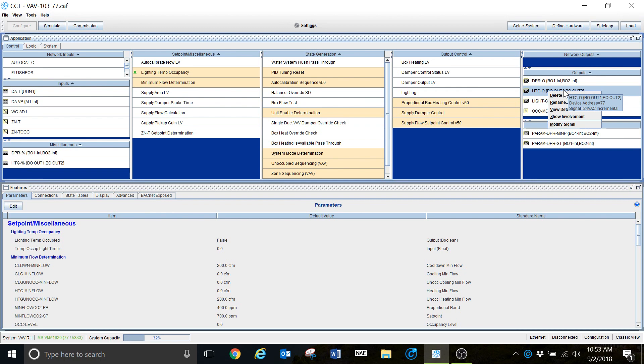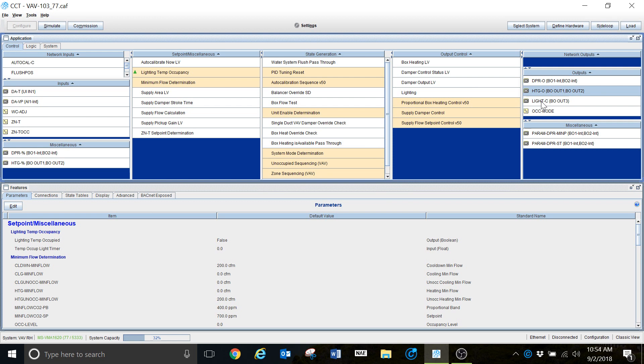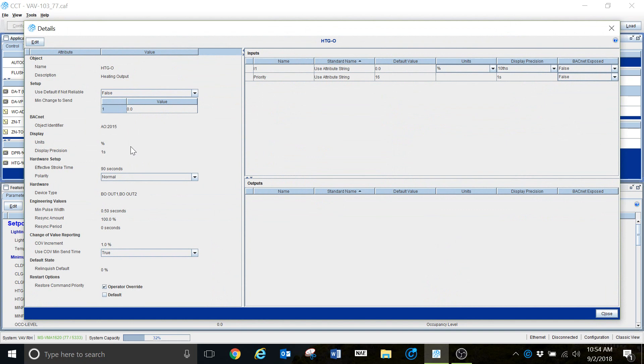From this window I can go into View Details, and it will show exactly what this is. You can modify this if necessary. For example, if I wanted to reverse the direction of this actuator, I'll hit the Edit button, and then depending on the actuator and the valve, I can reverse the direction that the actuator travels right here. It's very simple to do that. It's also going to give you some other information — you can rename it and that sort of thing. We're just going to cancel out and close this window.